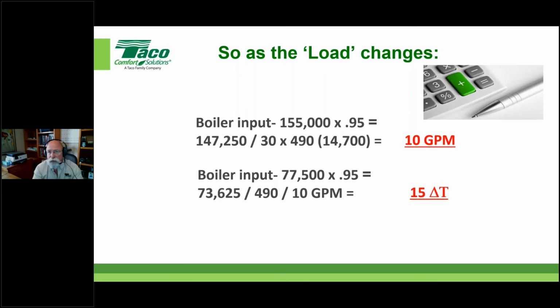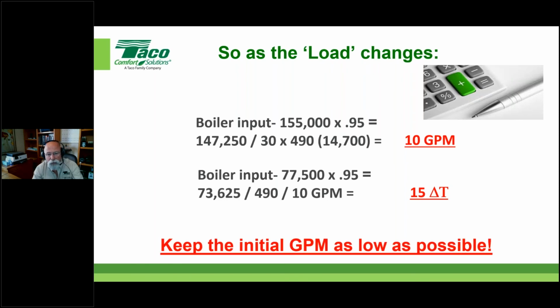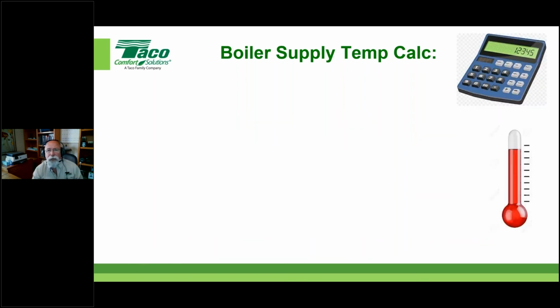But for the most part, this is how to anticipate a fixed speed pump. Now, again, even if I'm using a circulator that has 0 to 10 and the boiler's controlling it, you can't ever go any lower than low. So that's why it's still very important to get the circulator sizing drilled in, get it pinpoint, dot your I's and cross your T's on this thing, because it'll pay dividends in the longevity of the overall system efficiency. So again, keep it as low as possible.